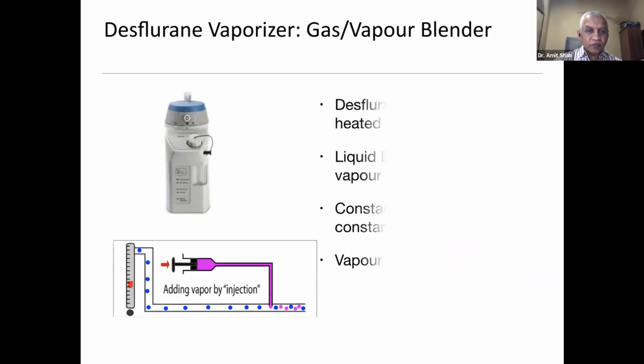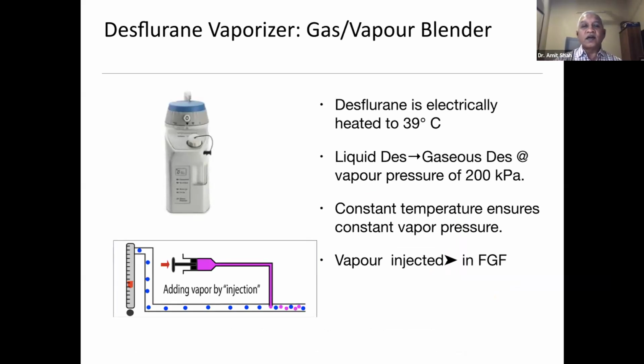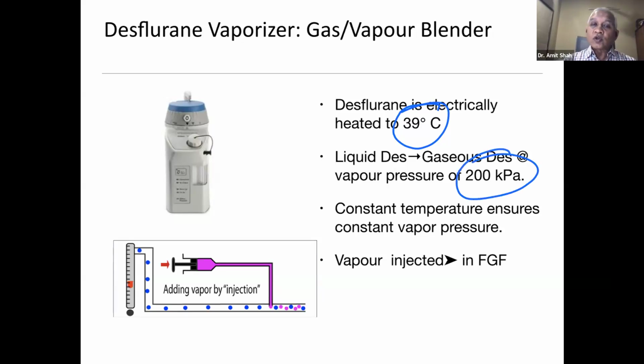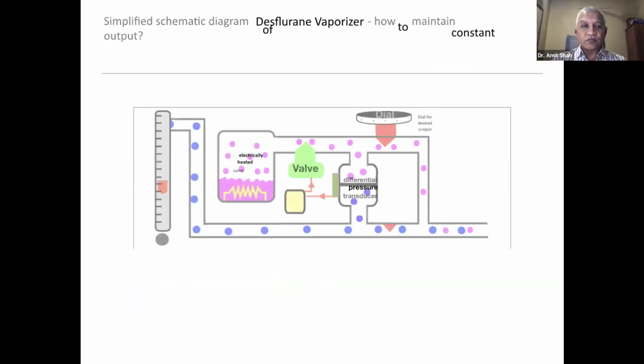So what they have done is electronically heat the desflurane vaporizer. That is why the desflurane vaporizer needs to be put into an electric socket to heat it. You connect it, and it will take some time to heat the vaporizer chamber to 39 degrees centigrade. At 39 degrees centigrade, the vapor pressure is actually 2 atmospheric pressure or 200 kPa. So now it is heated at 39 degrees constantly, the vapor pressure is quite accurate, and this vapor is directly added into the fresh gas flow.